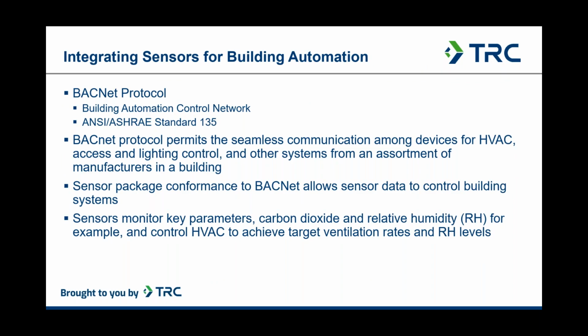Integrating this sensor data into building automation is really where everything is going. An important protocol is what's known as the Building Automation Control Network, or BACnet protocol for short. This is an ANSI ASHRAE standard. Essentially what the protocol does is it allows for seamless communication among a variety of different systems in the building and the information that sensors produce. So a sensor package that conforms to BACnet allows the sensor data to control building automation systems.